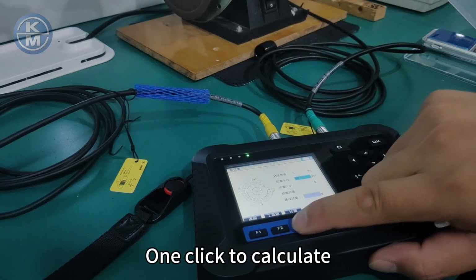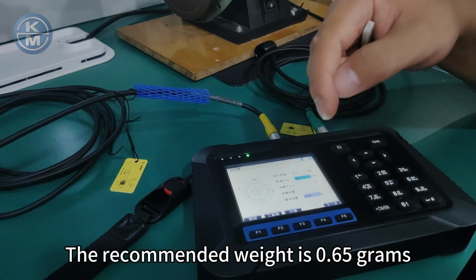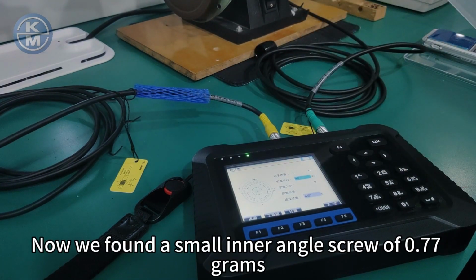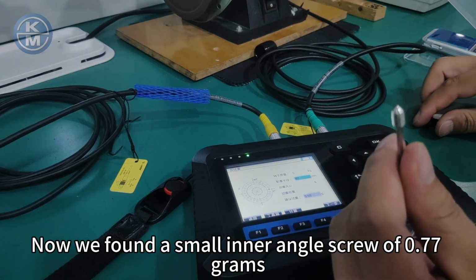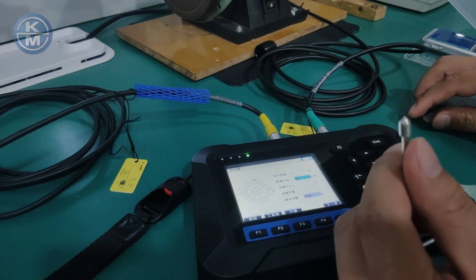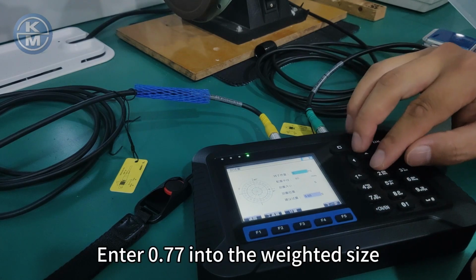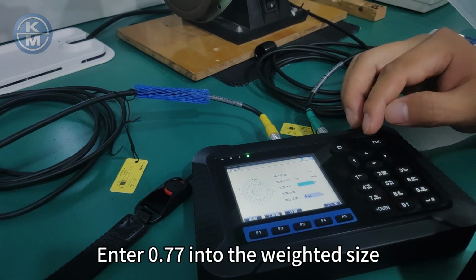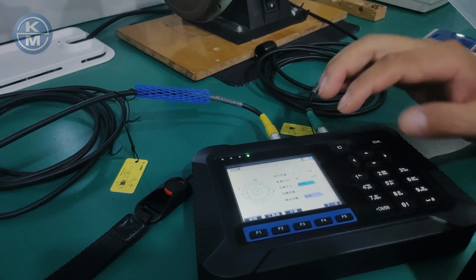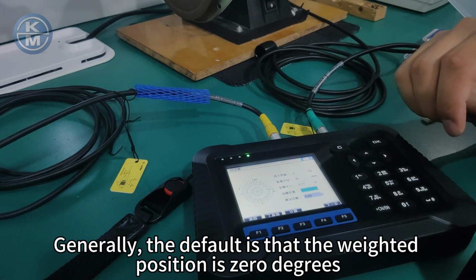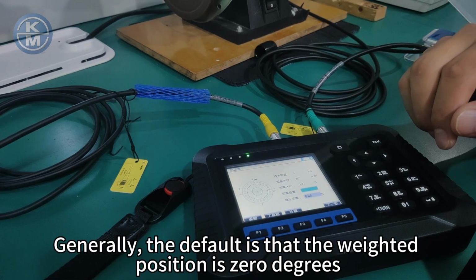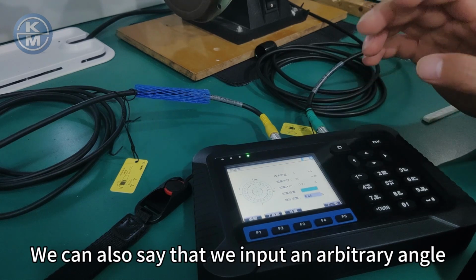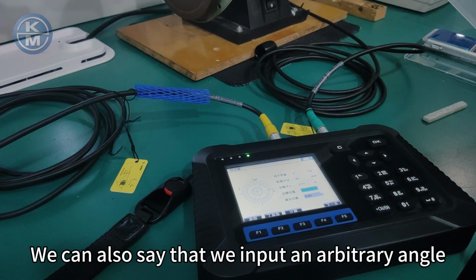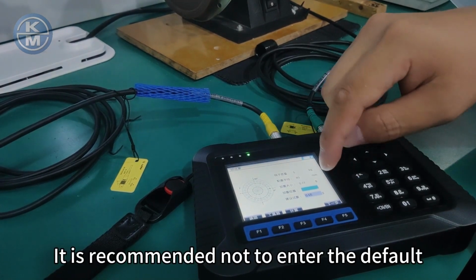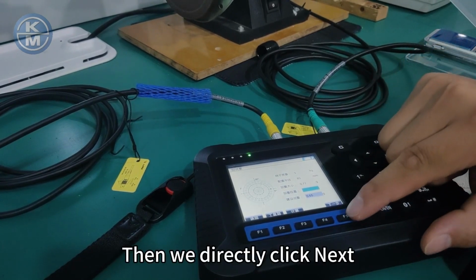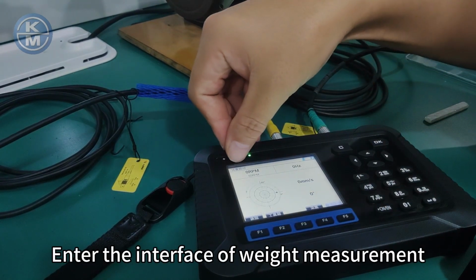One click to calculate. The recommended weight is 0.65 grams. Now we found a small inner angle screw of 0.77 grams. We add it in. Enter 0.77 into the weight size. Generally, the default is that the weighted position is 0 degrees, so we don't have to type. We can also input an arbitrary angle, but it is recommended not to, and to keep the default. Then we directly click Next to enter the interface of weight measurement.